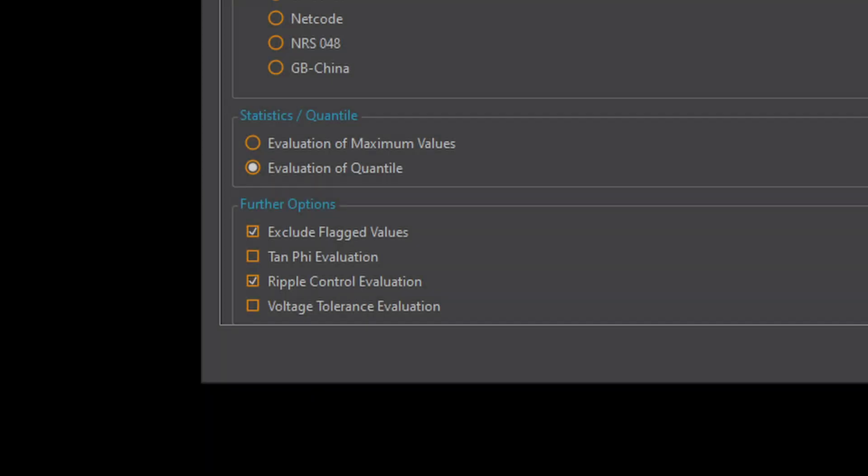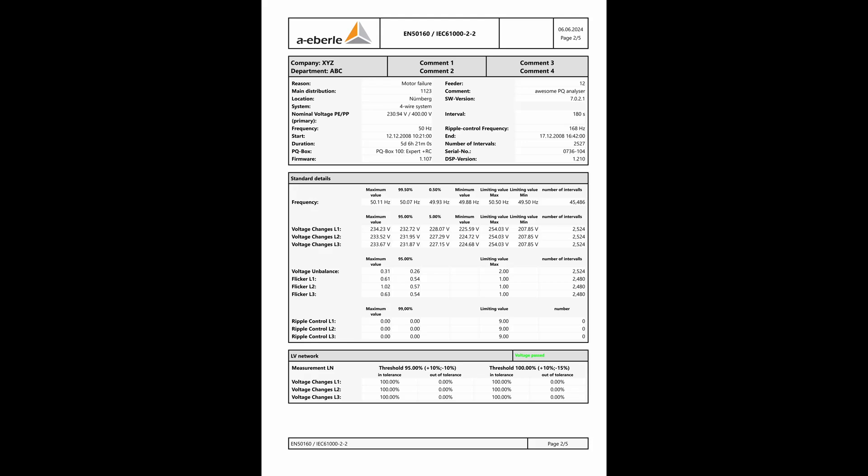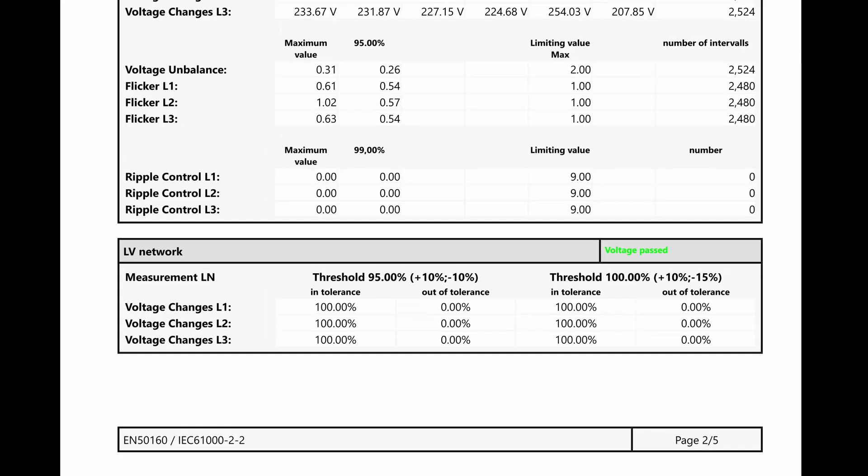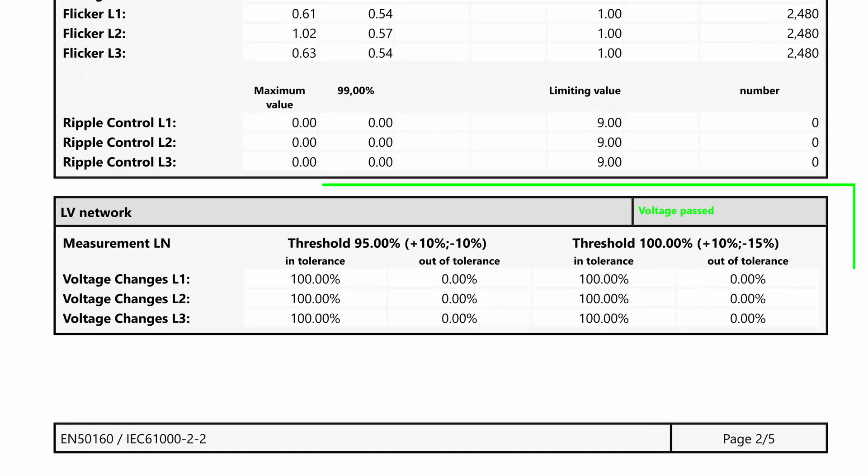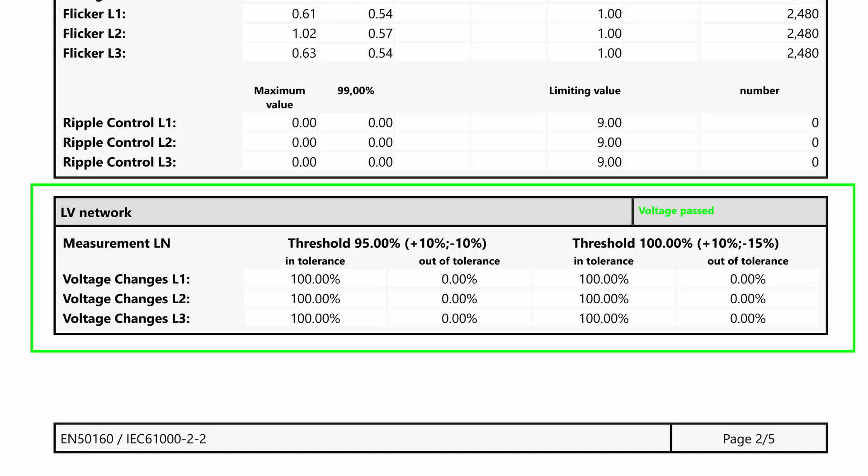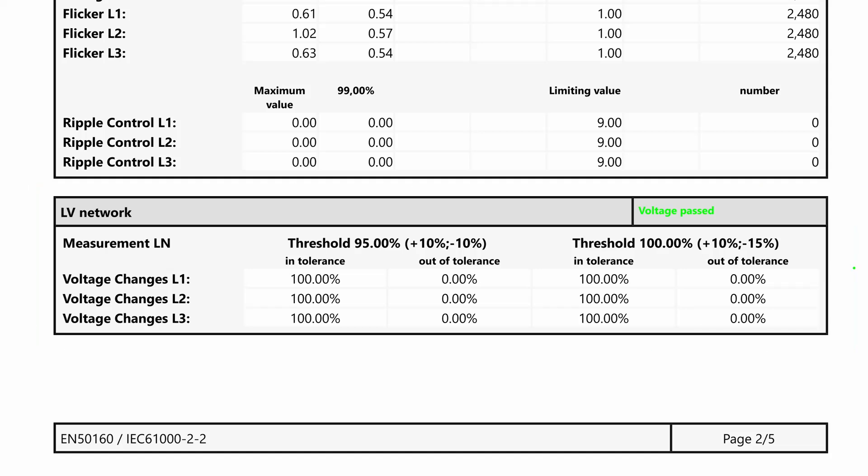If I want to evaluate the voltage tolerance I activate the corresponding item. WinPQ Mobile now generates a table in the report. There I can see how many measured values are within and outside the tolerance bands for the nominal voltage.